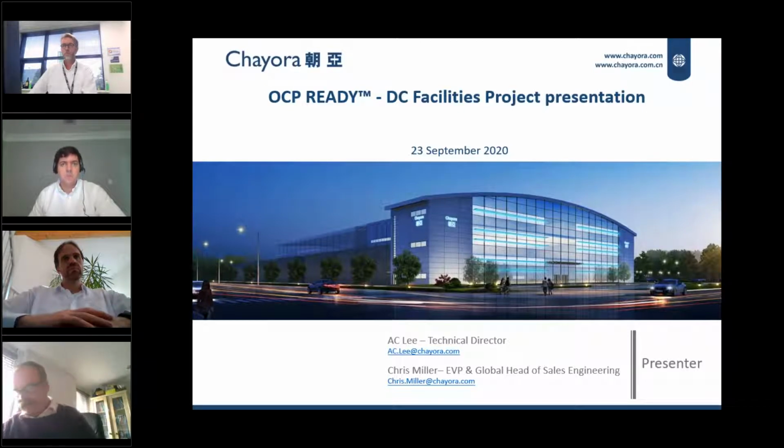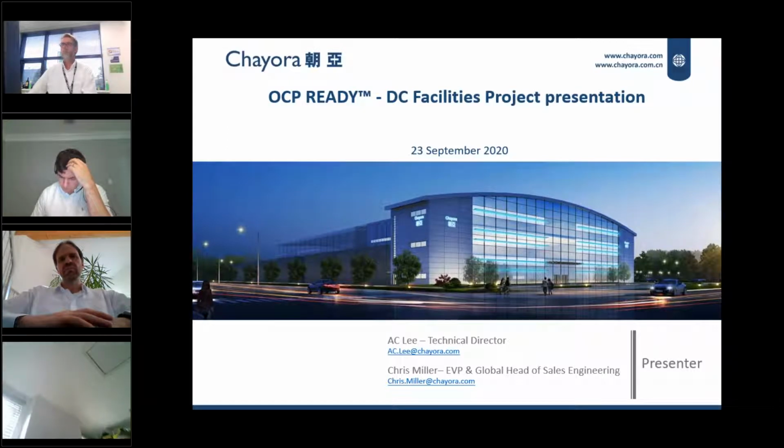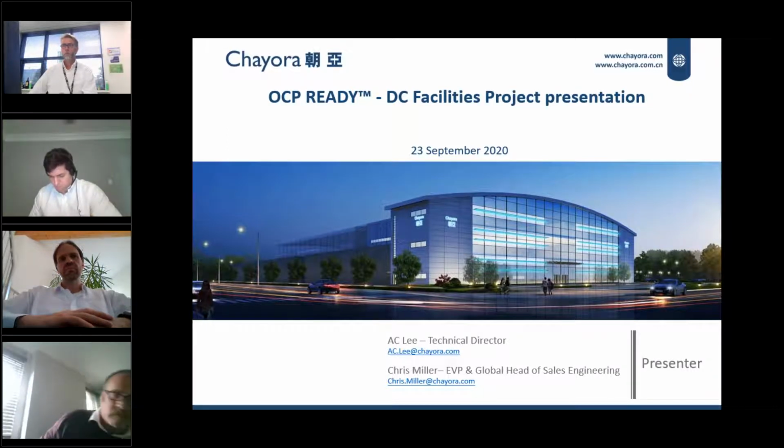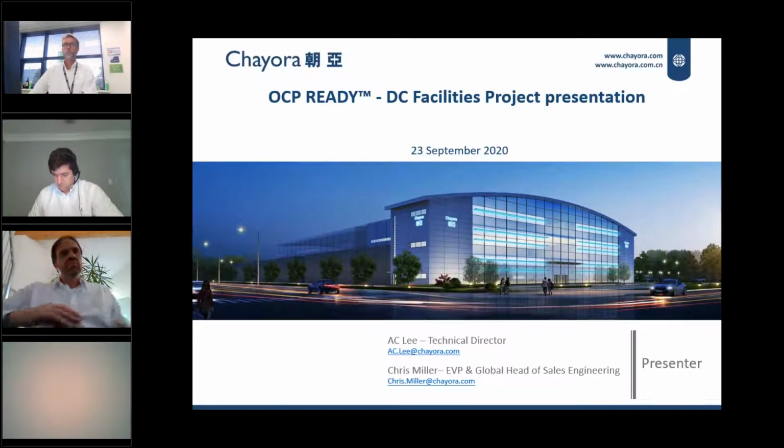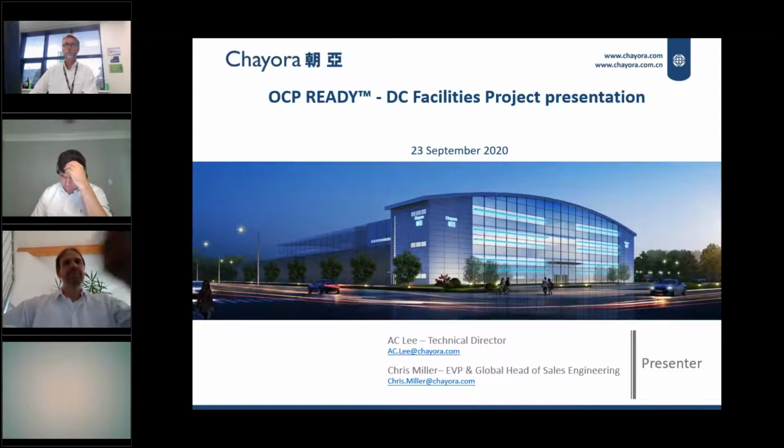So specifically, you guys talk about liquid cooling, right? What we have in this site is a dry cooler that does a pre-cooling on the site. We employ 18 degree chilled water, or condenser water. So should you use any of those water cool, we can hook up directly to our dry cooler system. So we're ready for liquid cooling technologies on the get-go, because we have nipple points from our pipes that we can link up to liquid cool systems if and when required.